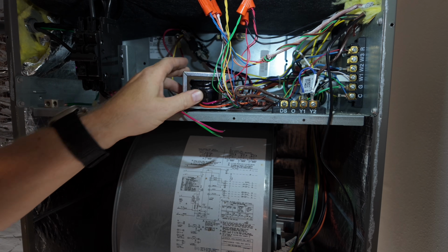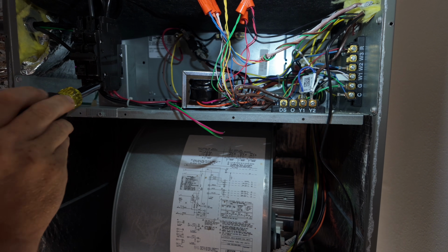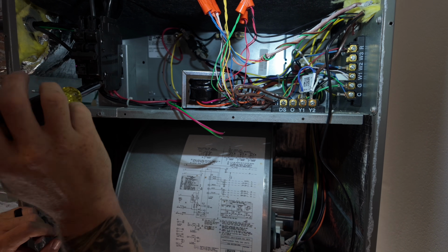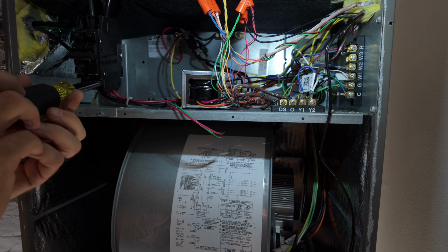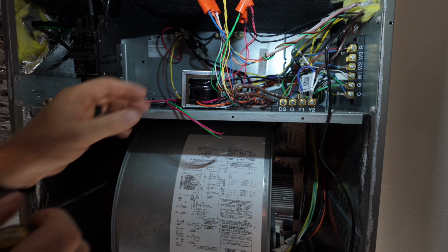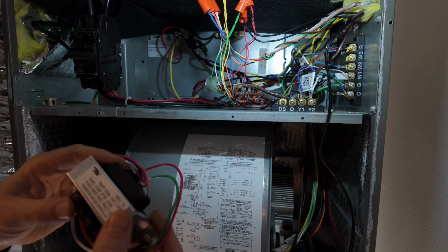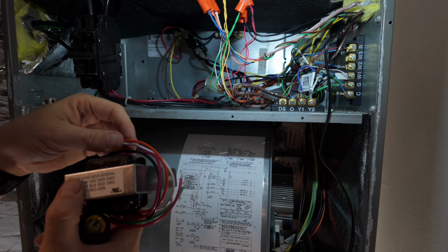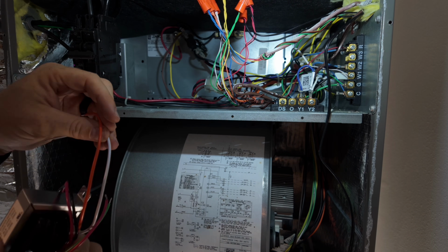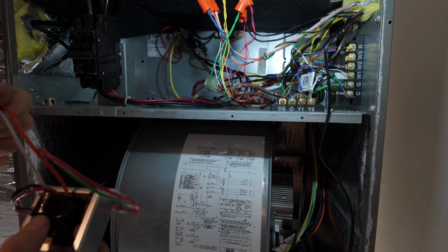Being that this is a universal transformer, white is our common, orange is our 240. So each leg is going to end up carrying that 120 volts. So I'm just tapping directly into the bottom of this breaker, one side with orange, one side with white, torque it down and make sure we're nice and tight, that way we don't have any issues.